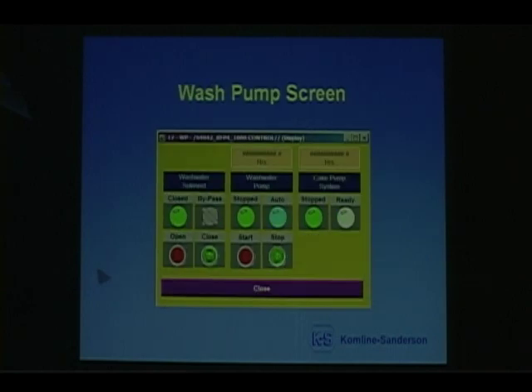And then you've got your wash water pump screen that pops up. On your wash water pump screen, you've got your hour meters for the cake pump and for the wash pump. You've got your start stop buttons, your running light. Then you've got what they call a bypass on the wash water solenoid. This is something Bob Maynard wanted. When you get a belt misalignment, you can put it in bypass and the water will continue running. If you touch it again, it will go into the normal mode that you'll be running when you're running the press.